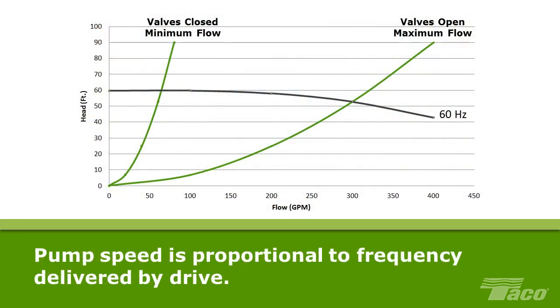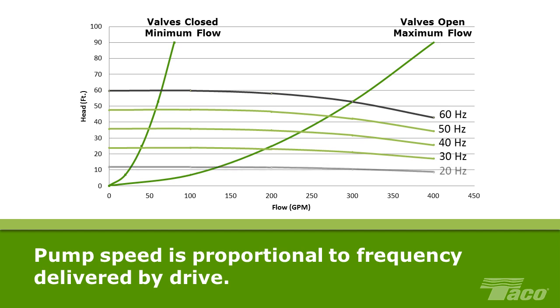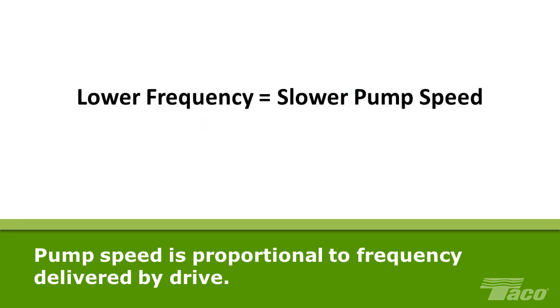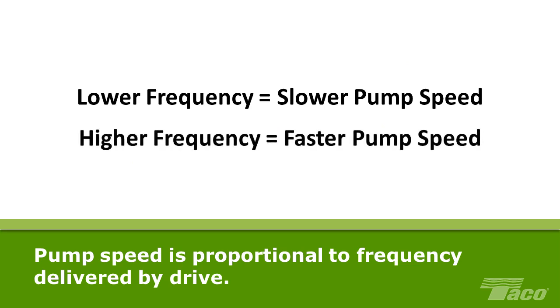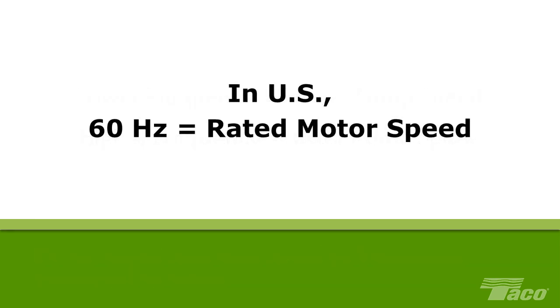For a pump with a variable frequency drive, such as the Taco SelfSensing pumps, pump speed is proportional to the frequency delivered by the drive. Lower the frequency delivered by the drive, and you lower pump speed. Raising the frequency causes the pump to pump faster. In the US, electrical power is delivered to the building at 60 Hz. Therefore, the rated speed for the motor is at 60 Hz.